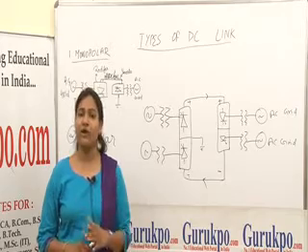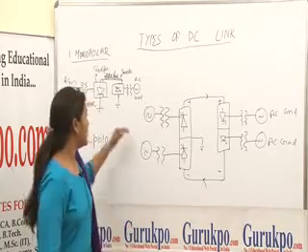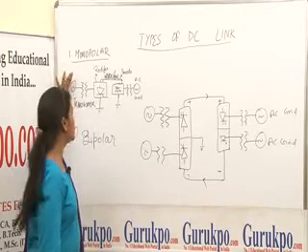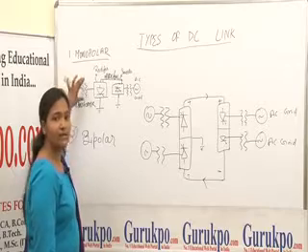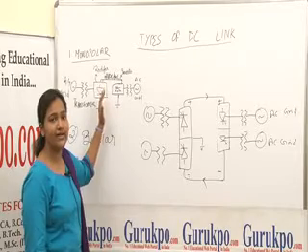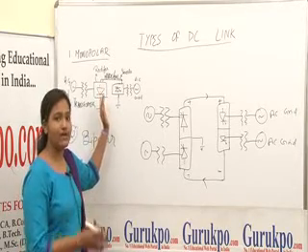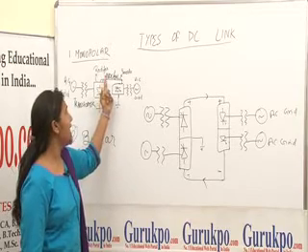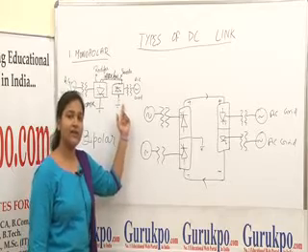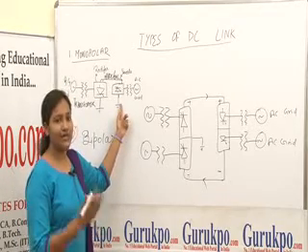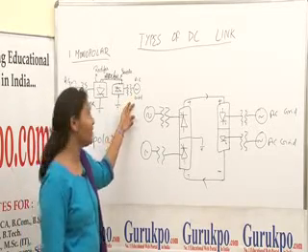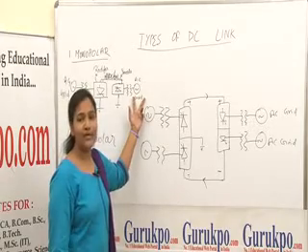And the positive polarity can be obtained from the ground. In this way, monopolar links work. First of all, we have an AC source. The AC source transmits AC power to the transformer, where it is stepped up and provided to the rectifier section where it is converted from AC to DC. This high voltage DC is then transmitted over the high voltage DC line to the inverter section, where it is converted from DC to AC. This converted AC is provided to the step-down transformer where the voltage levels are stepped down, and then it is provided to the AC grid system.